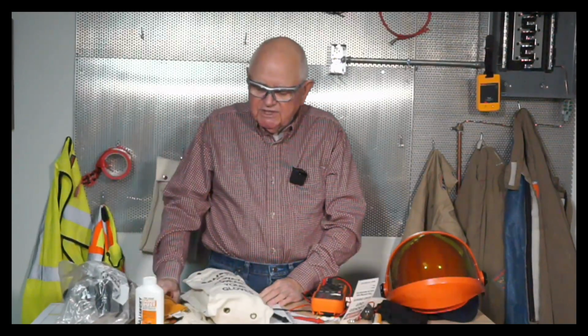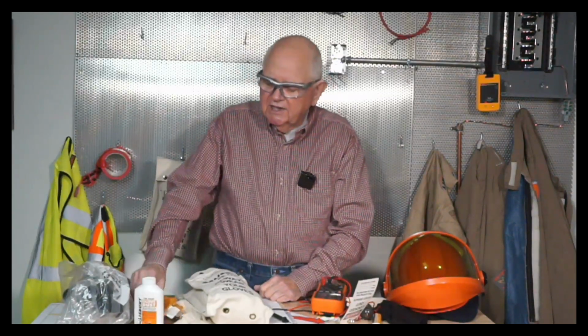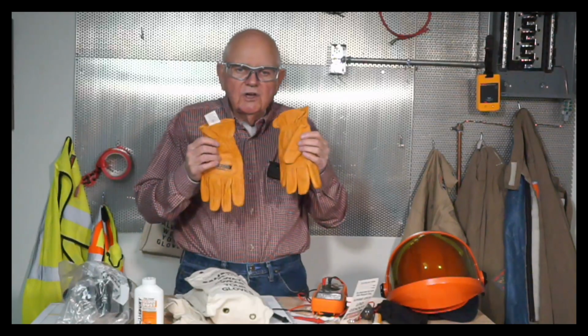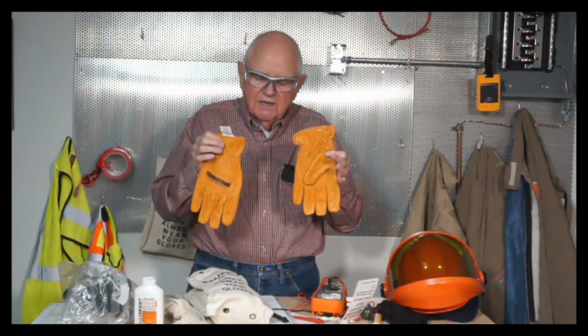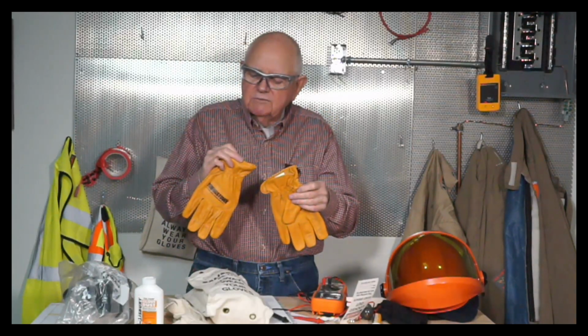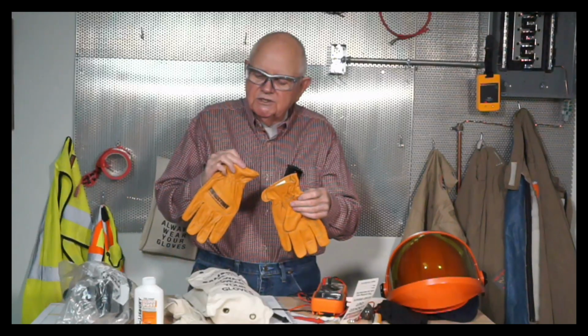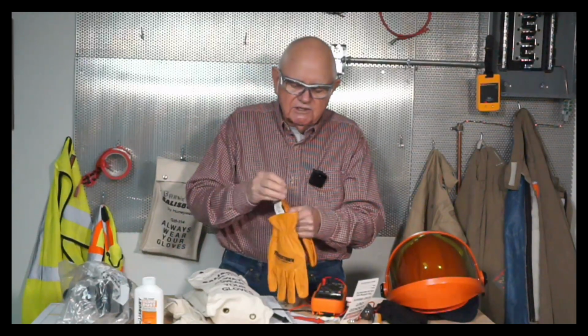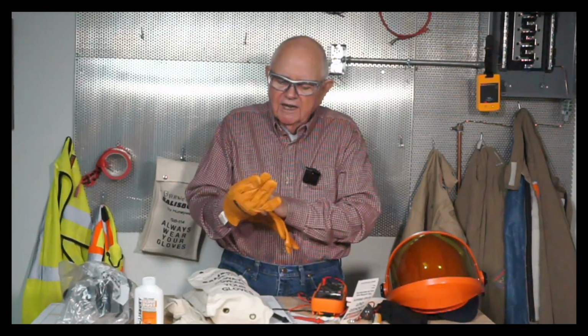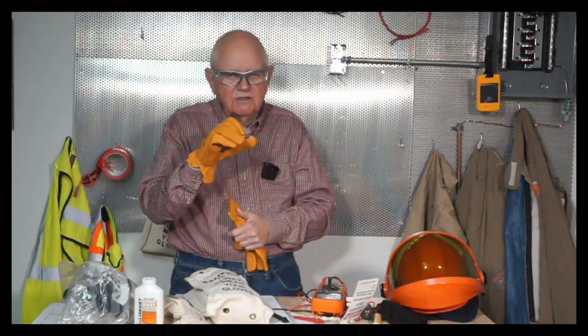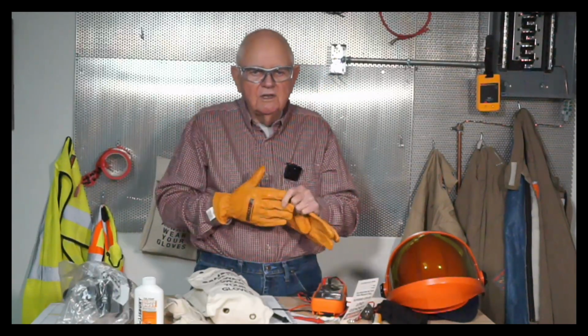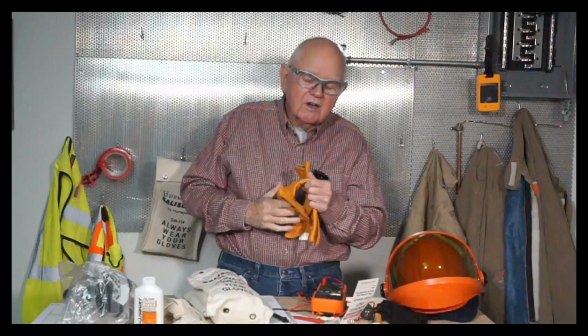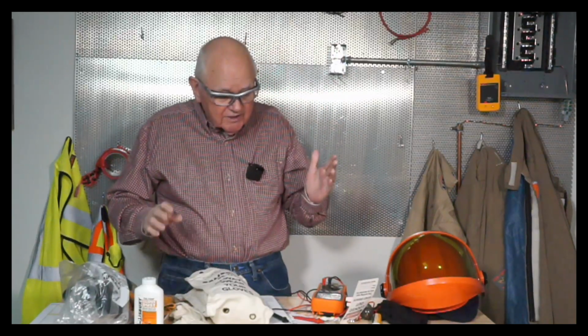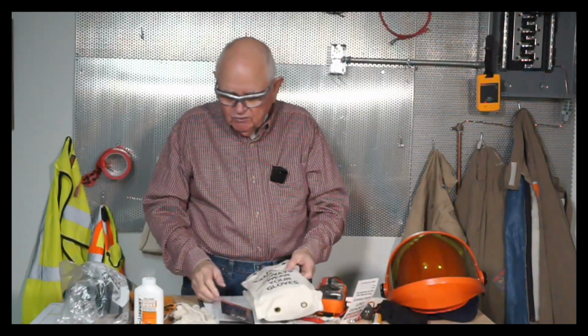For arc flash protection, I can use my rubber gloves. Take a look at your policy, the 70E standard, see what it has to say. These are leather gloves. They're rated, it says on here, ATPV 27 calories. And they call them ground gloves. But they're nice, soft leather gloves. And so they give me no shock protection. But if I don't need shock protection, they're good for up to 27 calories of arc flash protection. So whatever it is you need to wear, make sure that you wear it then.